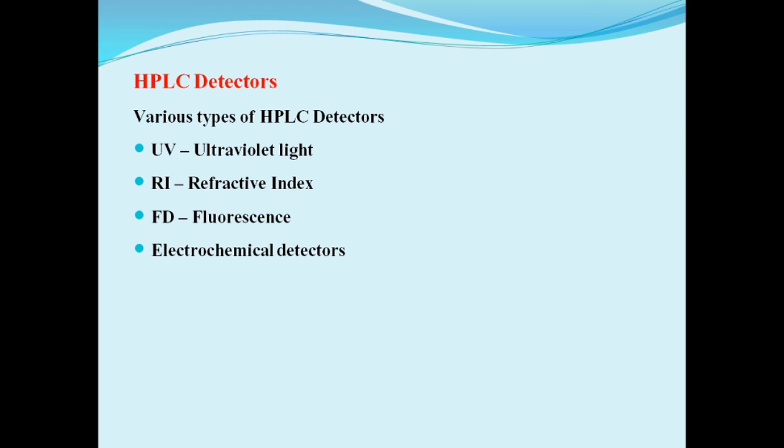Next, the HPLC detector is the electrochemical detector. Normally refers to amperometric or coulometric detectors. Principle: measure the current associated with the oxidation or reduction of solute. The detector usually contains a low volume cell through which the mobile phase passes carrying the sample component.